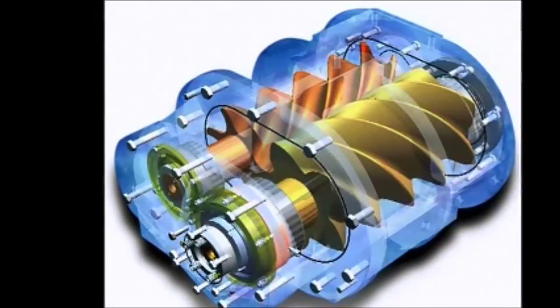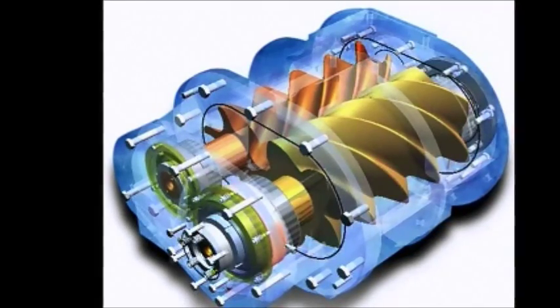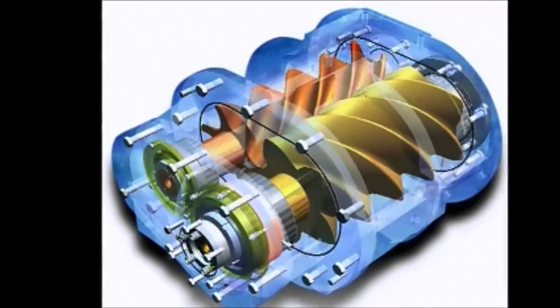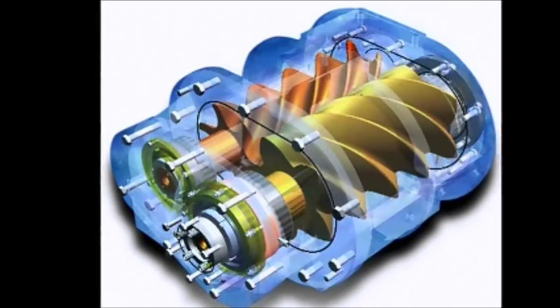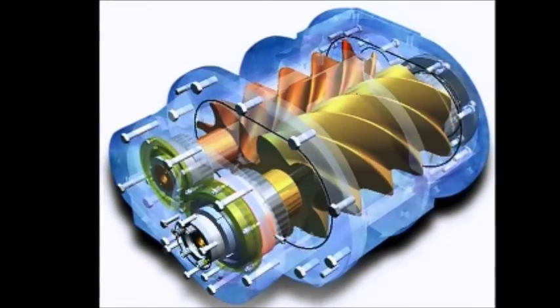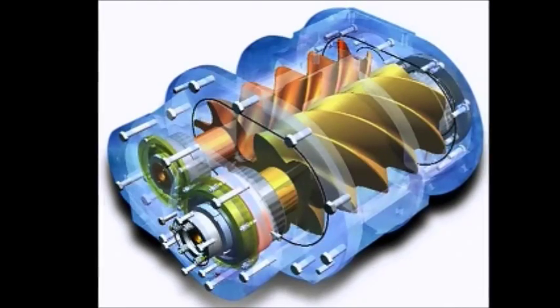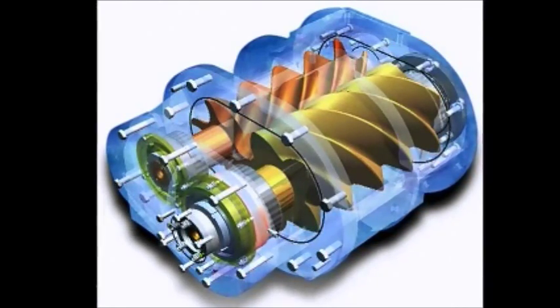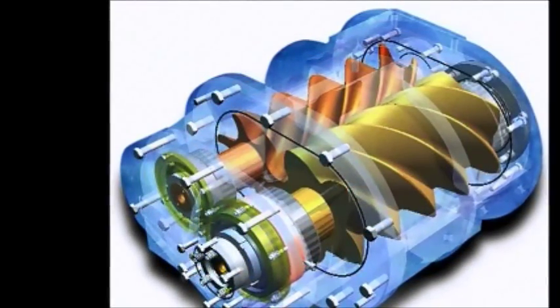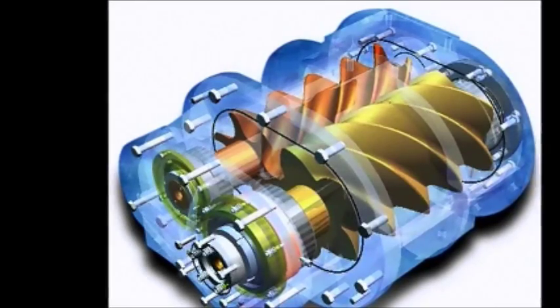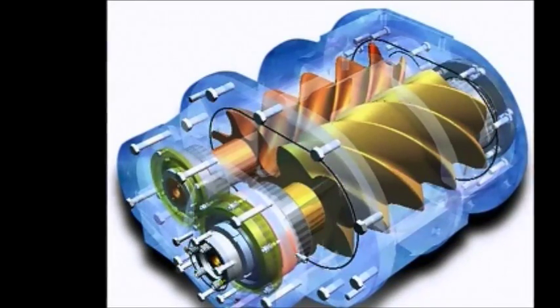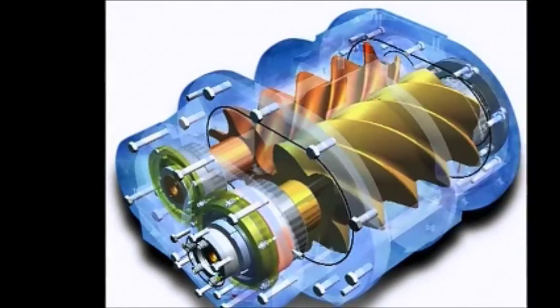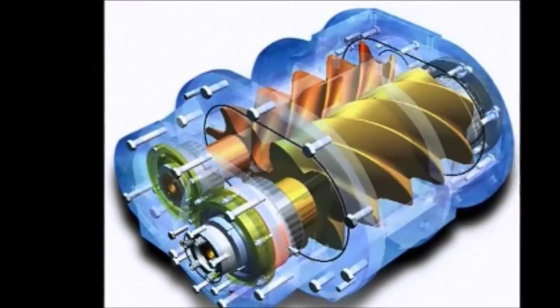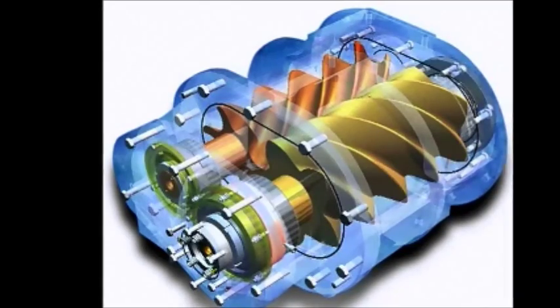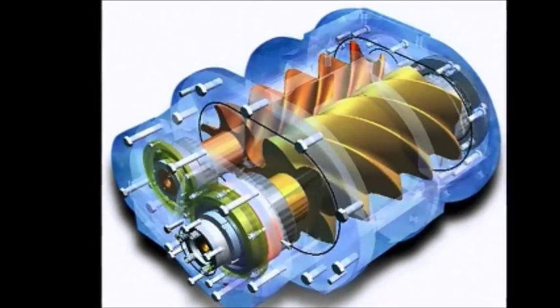The blue case is precision machined with an air inlet port and a pressurized air exhaust port. The casing surrounds and supports two high-speed precision rotors highlighted in yellow and orange, which are supported at each end by ultra-precision high-speed roller bearings. Input power rotates the yellow rotor, and in turn the yellow rotor drives the orange rotor. Although the rotors may appear to be touching each other with the naked eye, they are separated by a micro gap, and the same goes with the rotor clearance with respect to the case.